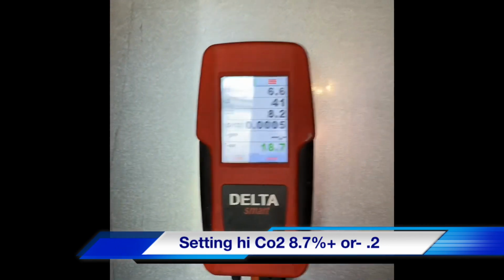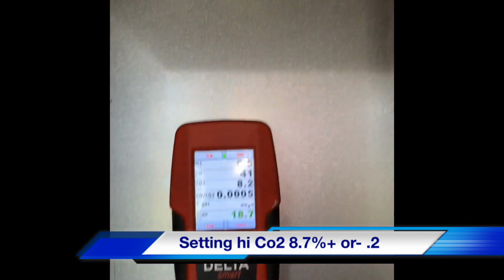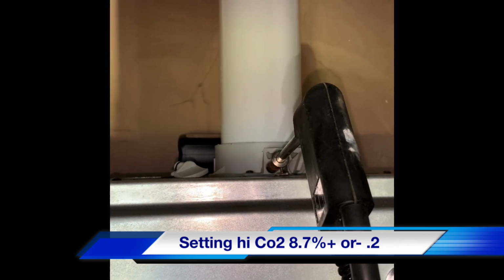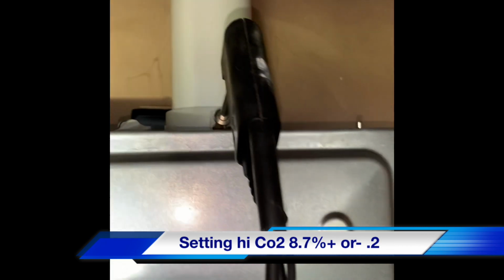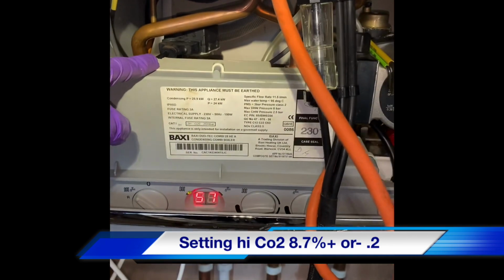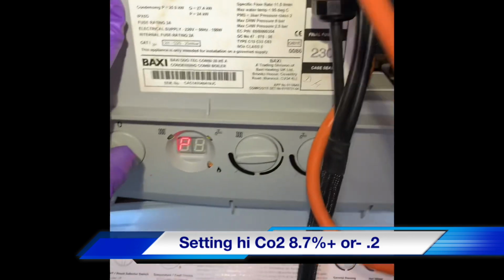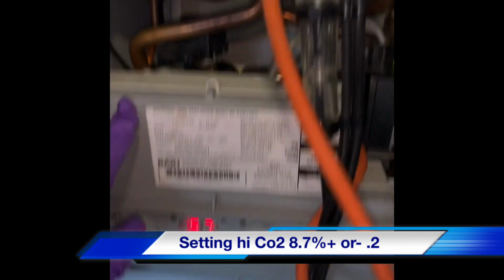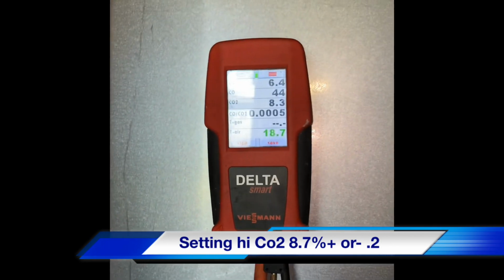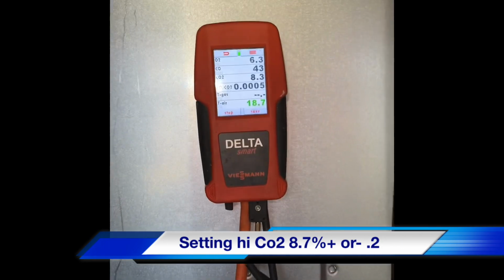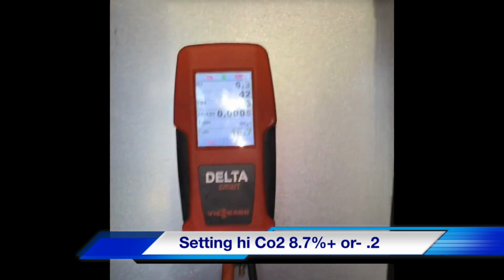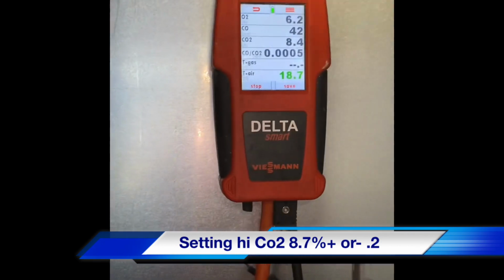Right, so we're just carrying out our 26.9 flue performance checks. As you can see, analyzer and flue sample point. We've got the fan running flat out. So as you can see, the fan's running at its fastest setting. So in this particular mode, we should be looking for about 8.7 plus or minus 0.2.